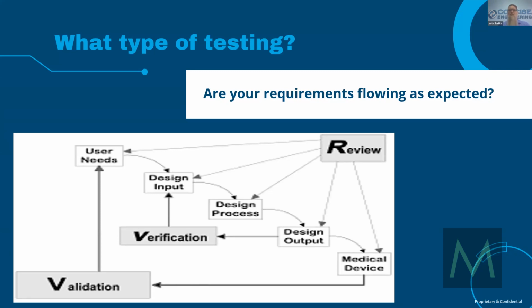And so the reason I bring this up is because I get down here to design outputs. Now I know what to verify. Well, if I messed up everything before that, I'm going to lose, right? So bad user needs, bad design inputs. I miss a bunch of features that are required. I test the output. I couldn't possibly be successful, or I could be, and my product is still terrible. So having more folks look at this over time, through these reviews, through cross-functional teams, is going to help you identify why this product is likely to be successful or unsuccessful when it gets into the field.